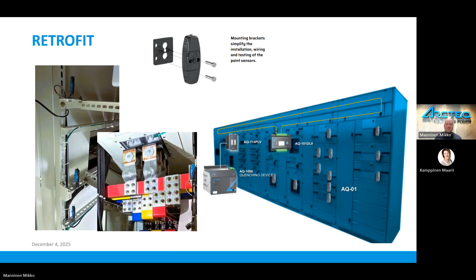Then integrating this Modbus to the SCADA, DACS, any control or automation system. Well, let me tell you. Yes, the most common approach has been and is to utilize the AQ250 series alarm annunciator, like this one here, or any other AQ250 series relays as a Modbus master. So this is the master who asks questions from these ArcFlash relays. And this AQ250 here also serves as a protocol gateway to connect with other systems seamlessly. For example, if you get Modbus RTU here, you can talk to the SCADA with some other protocol. In this example, for example, 61850.